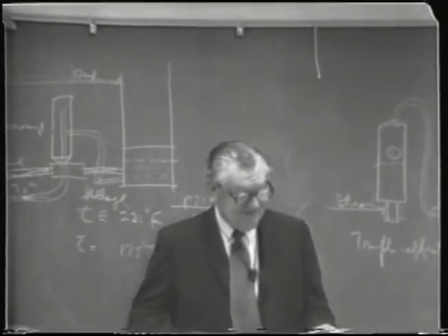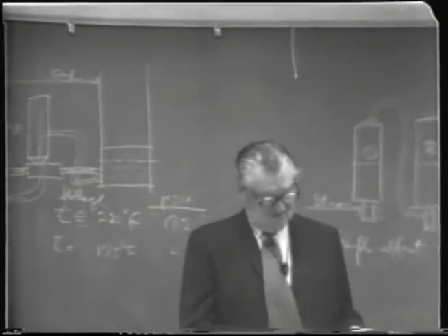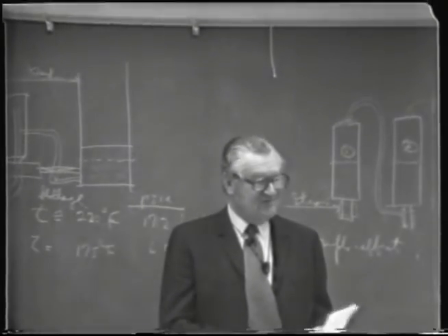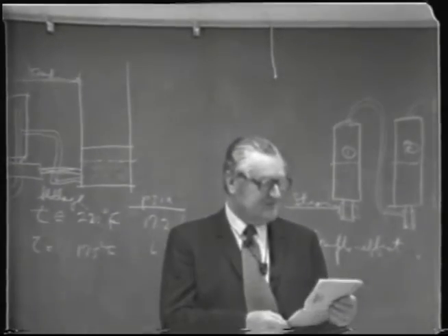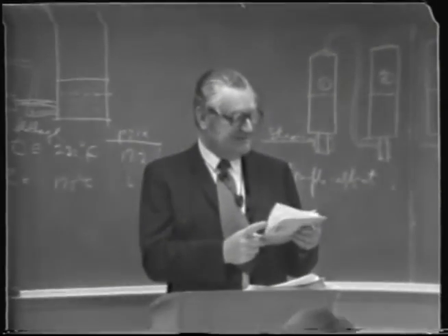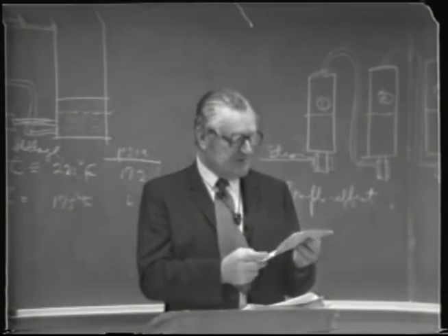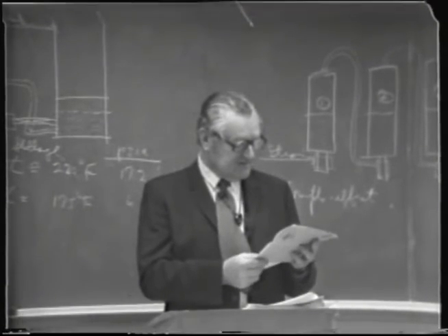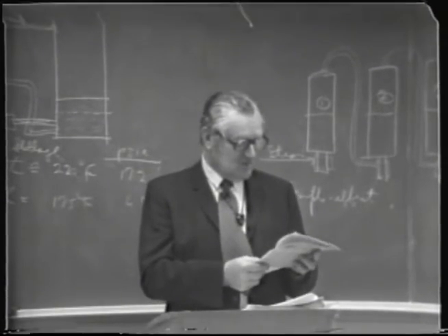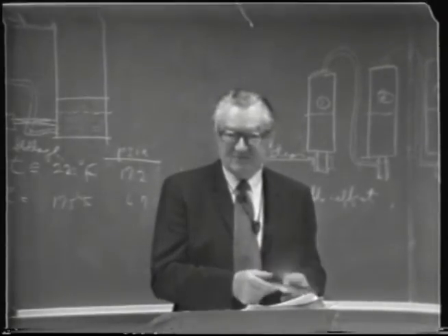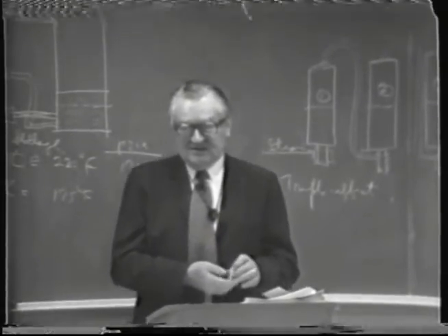If you want to drop it down to 120 degrees Fahrenheit, which might be a reasonable discharge temperature, how low a pressure would you have to get? Well, it'd be almost impractical to get. It'd be impossible to get it. Be impractical and also impossible. 1.7 pounds per square inch absolute. So you can't obtain that in these type of devices.